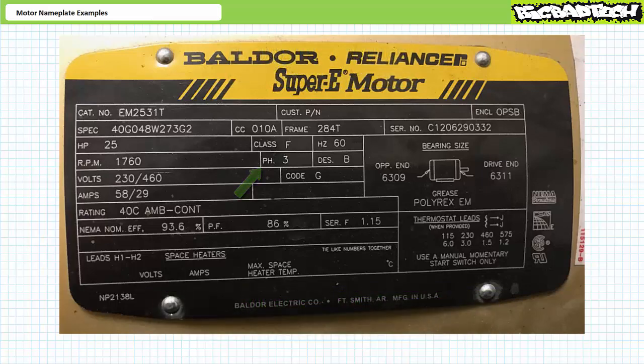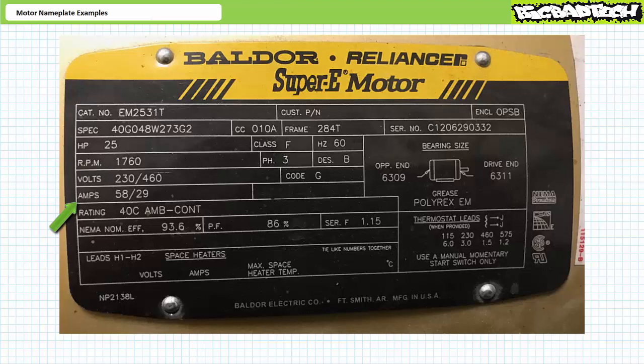It looks like this is a three-phase motor intended to operate at 60 Hz. It appears to be a dual voltage motor that can operate at 230 volts in the low voltage configuration and 460 volts in the high voltage configuration. In the low voltage configuration it draws 58 amps at the rated condition, whereas in the high voltage configuration it draws only 29 amps. At the rated condition it has a power factor of 0.86 and operates at 93.6% efficiency. The inrush code appears to be G.